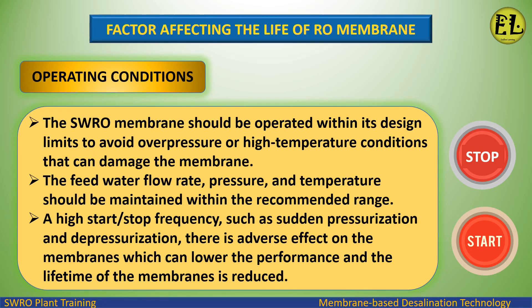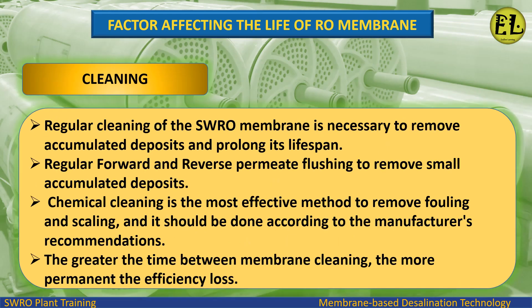The SWRO membrane should be operated within its design limits to avoid overpressure or high temperature conditions that can damage the membrane. The feed water flow rate, pressure, and temperature should be maintained within the recommended range. A high start/stop frequency — such as sudden pressurization and depressurization — has an adverse effect on the membranes, which can lower their performance and reduce their lifetime.